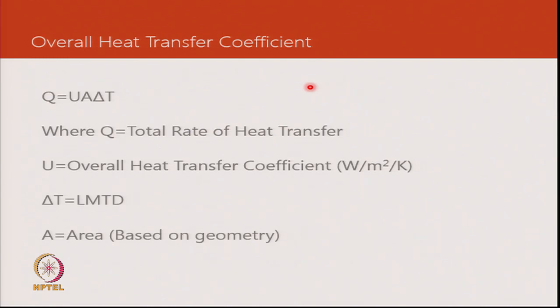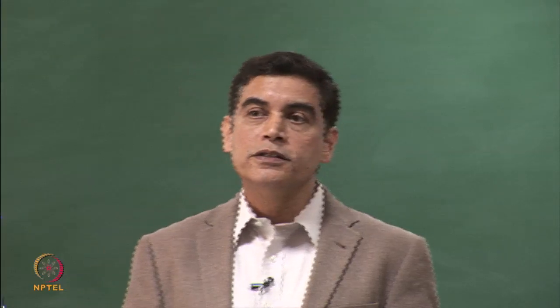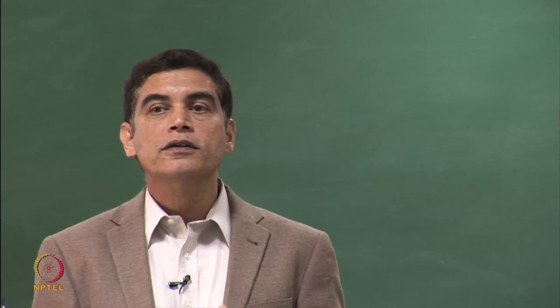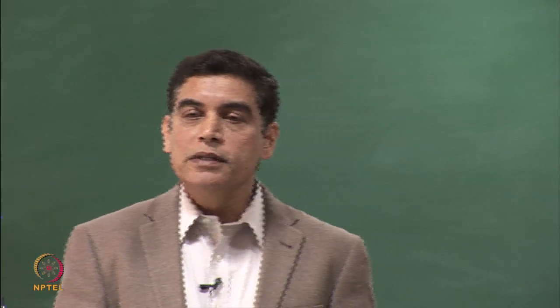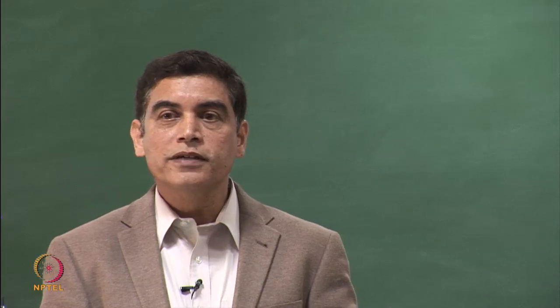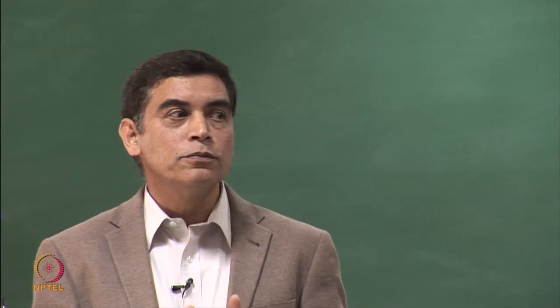The governing equation is, the overall governing equation is overall heat transfer coefficient times area times log mean of the temperature difference at inlet and outlet. There is something more complex than this, because the evaporator does not have a constant temperature profile. Let us say comfort application, return air entering at 27 degrees centigrade dry bulb, 19 degrees wet bulb. When it first comes in contact with refrigerant, the bank of tubes which are the first contact point, we will have only sensible heat transfer. There is no mass transfer happening till that air reaches the dew point.